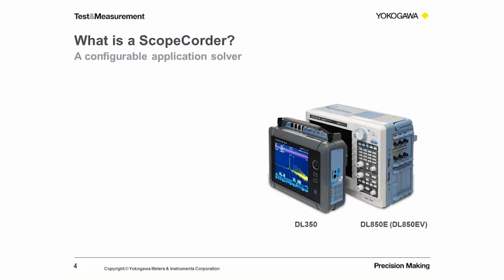So, trying to answer the question, what is a ScopeCorder? Well, as we say here, it's a configurable application solver. We are now offering a range of 2 or 3, if you consider the DL850 as 2 instruments. We've recently introduced the DL350, which is essentially a more portable version with a rechargeable battery pack, which offers most of the functionality of its larger brother, the DL850E and the DL850EV. And I'll explain those differences as we go along.